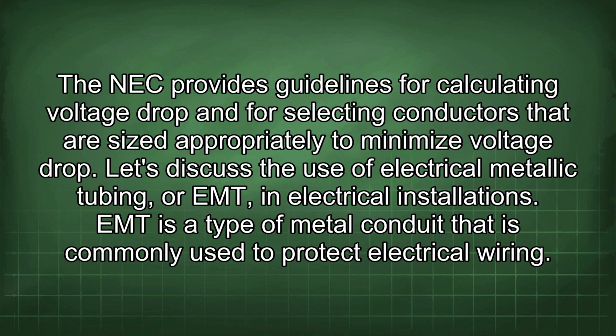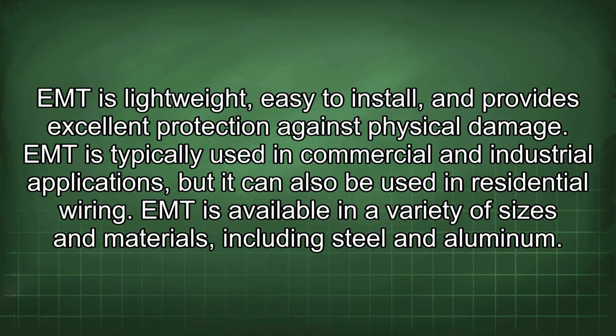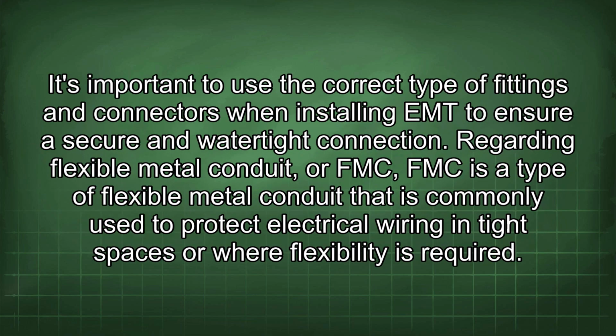Let's discuss the use of electrical metallic tubing, or EMT, in electrical installations. EMT is a type of metal conduit that is commonly used to protect electrical wiring. EMT is lightweight, easy to install, and provides excellent protection against physical damage. EMT is typically used in commercial and industrial applications, but it can also be used in residential wiring. EMT is available in a variety of sizes and materials, including steel and aluminum.